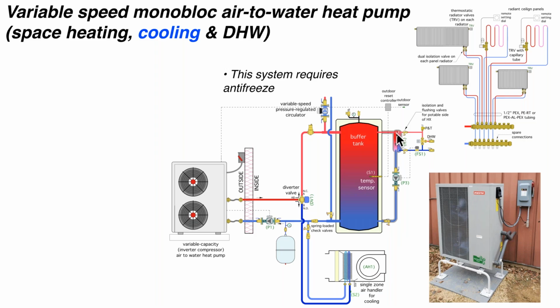How much heat does it get? You've got to do the calculations on this. The size of the heat exchanger will certainly matter, as well as what the flow rate is, what the temperature of the buffer tank is. But there's online software to help you with that.